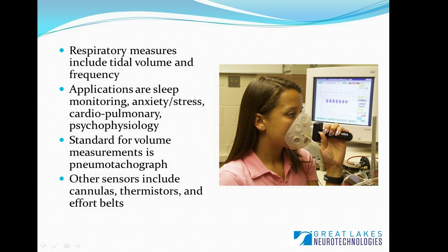A very common type of respiratory measurement is volume. Currently many people use what's called a pneumotachograph — a face-worn sensor similar to the picture on the right. It's a mask that goes over the nose and mouth, and that's what records inspiration and expiration to measure respiratory parameters such as volume. A few other sensors for measuring respiration include nasal-oral cannulas to measure flow rate and air flow using pressure changes, thermistors which use temperature, respiratory effort belts, and spirometers.